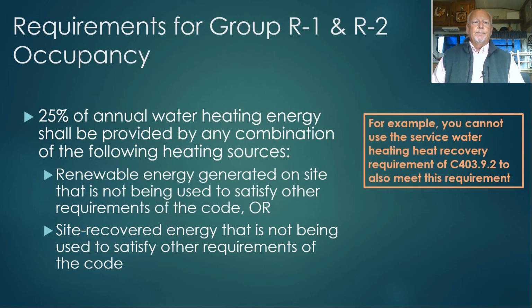So what is the requirement? The requirement is that 25% of the annual water heating energy shall be provided by any combination of the following. It shall be provided by either renewable energy generated on-site that is not being used to satisfy other requirements of the code, or site recovered energy that is not being used to satisfy other requirements of the code. For example, you cannot use the service water heating heat recovery requirements of C403.9.2 to also meet this requirement. So this 25% requirement is in addition to any other water heating energy recovery requirements that are in the code.